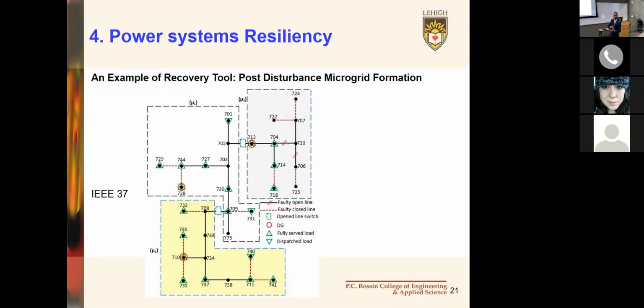To take into account flow constraints, some strategies include dispatching peaking turbines at substations, picking up the geographic area served by that substation. Dispatching intermediates, because you can fire those up in 5 or 10 minutes, pick up multiple substations so you can service that area, and come back up in smaller segments. Ultimately you have enough that you want to begin interconnecting the grid. But those are facilities that already exist.